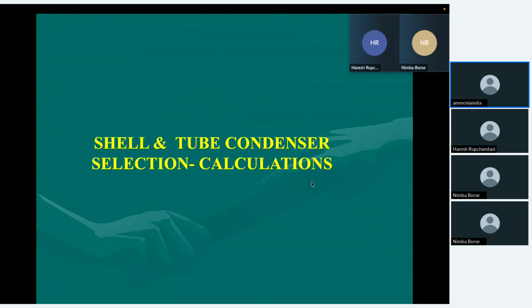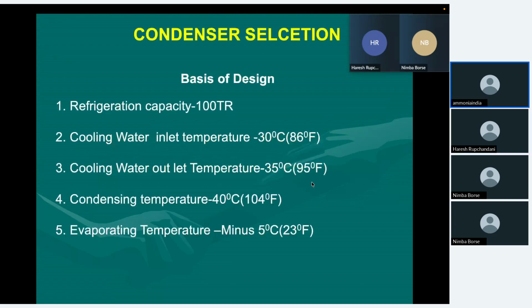Now we go to the shell and tube condenser selection calculation. We discussed how to construct the shell and tube condenser. Now we go to selection. Let us decide that we are going to select a refrigeration condenser of 100-ton capacity. The cooling water inlet is 30 degrees centigrade, outlet is 35 degrees. As I mentioned, condensing 40 degrees centigrade.